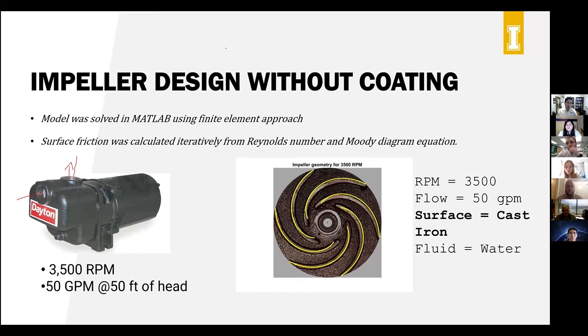Given that this pump actually does not operate in the field at design flow rate, most of these pumps are oversized just to satisfy future growth or just to be on the safer side. There is a possibility that if we change the impeller angle of pumps running at lower speed to deliver lower flow, we can improve efficiency very significantly. So without even coating, I think there is a big need to change this angle for lower speed operation of the pump. If that answers your question.